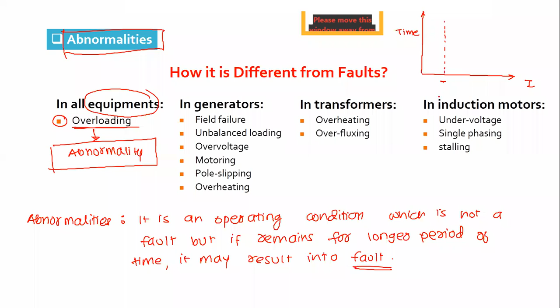So then, what are examples of abnormality? Overloading is an abnormal operating condition. It is an abnormality in all the equipment. Suppose an equipment draws overload current, because it is being overloaded, it draws more current than its rating. Then for some time it does not create any issue to the equipment. For example, let us take an induction motor. As I have said previously, we will consider the thermal withstand capability curve. Suppose this is the thermal withstand capability curve of an induction motor, which I am drawing here. This is the current, this is the time, and this is the rated current of the motor, let's say full load current.